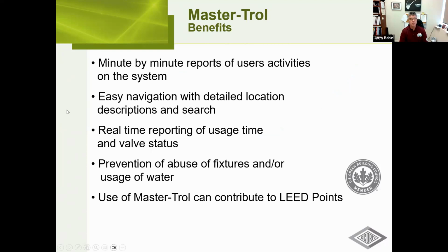Again, minute-by-minute reports of users' activities. It's easy to navigate with detailed location descriptions and search, real-time reporting of usage time and valve status, prevention of abuse to fixtures and or usage of water. And by that I mean that if somebody's using a fixture, say in the case of a security facility, and they're constantly flushing the toilets, you can actually limit how often they can flush the toilet and basically lock it out for whatever period of time. So maybe they're flushing it once an hour, and that's all the water usage they're going to have on that. And again, that's all done through our computer.